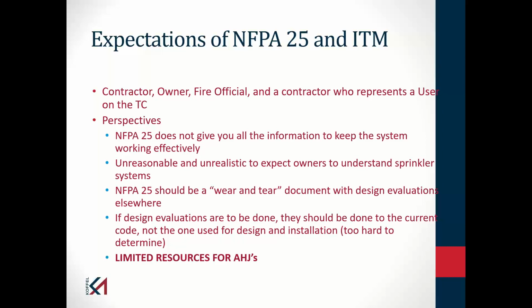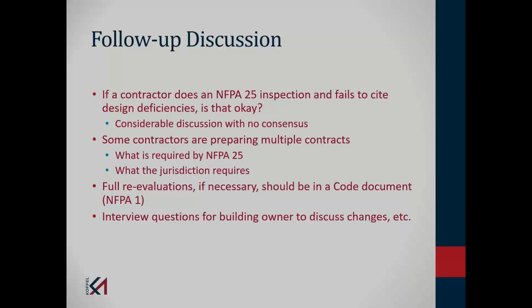So the message I'm delivering to you is, when it comes to design issues for your system, in particular for any changes that get made to your system, do not necessarily expect the inspecting contractor to verify that it's okay. Do not necessarily expect a fire marshal who might be doing an inspection. Again, I know campuses have their own fire marshal. It might be a little different on campus, but generally speaking, don't expect the fire marshal to do it. And I've already said I don't expect the owner to have this understanding of the design of the system. Again, I tried to highlight some of those.